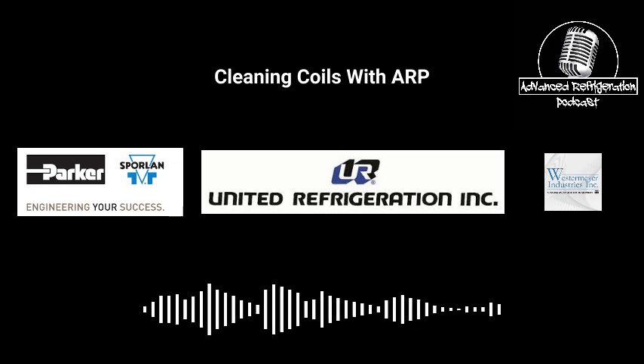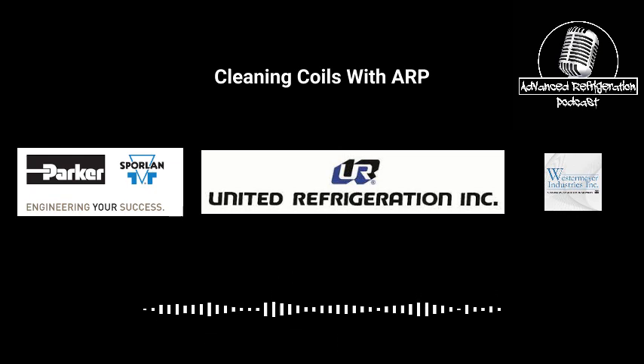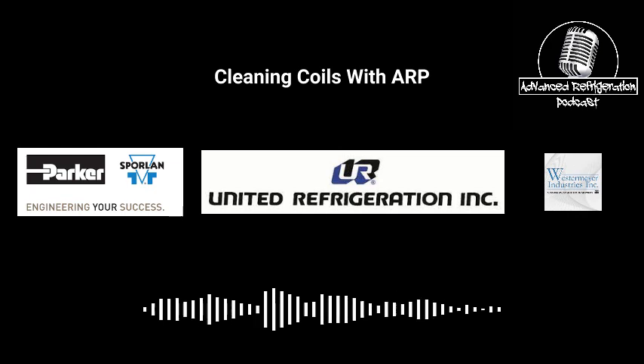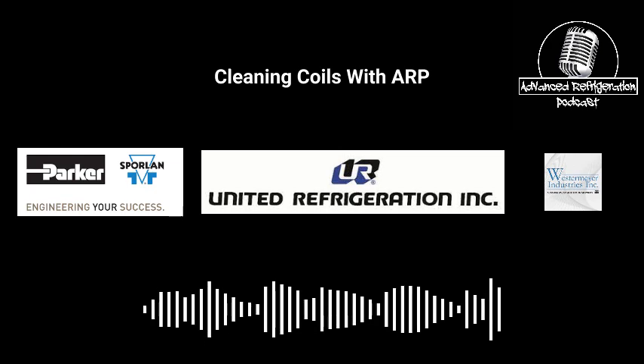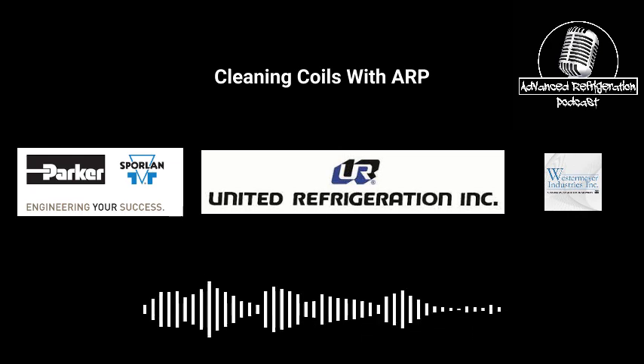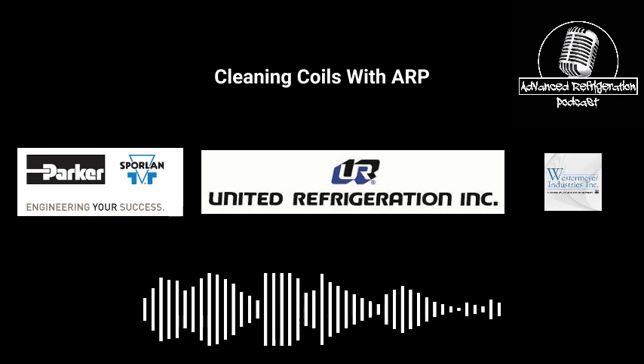You want to make sure you get those washed from the inside out on both of them. The outside coil you usually have to wash from the outside, pushing everything into the second coil. Then when it's split apart, you wash the other coil from the inside out, push everything down, and then rinse down. I see this all the time. Guys miss this on Trane and Carrier units and say, oh, I washed the coil and it's still messed up, this thing's impacted, it's destroyed, whatever. Then you go there and split the coils and you see blankets on the inside of both. And it's like, okay, that's great. This is not how it should be. You didn't clean the coil right.